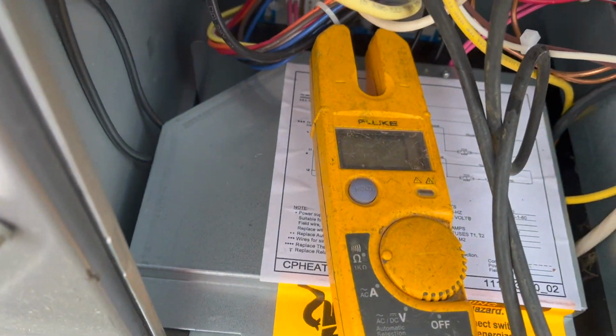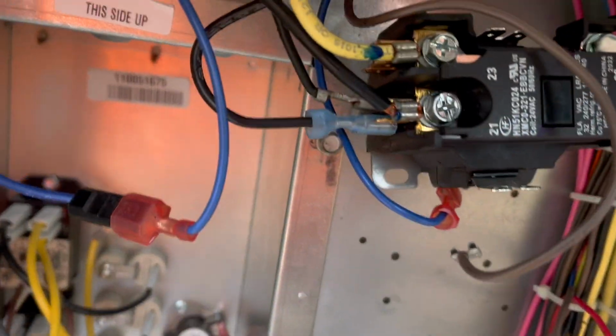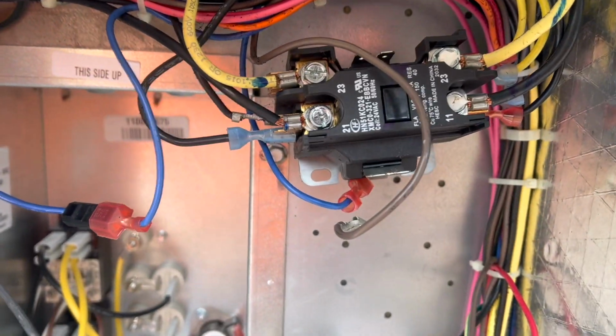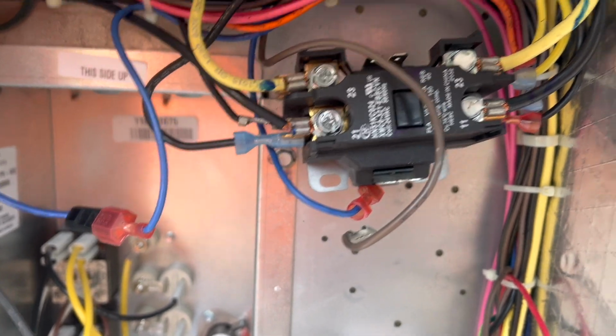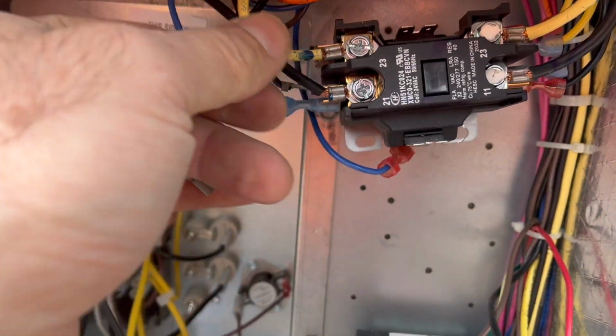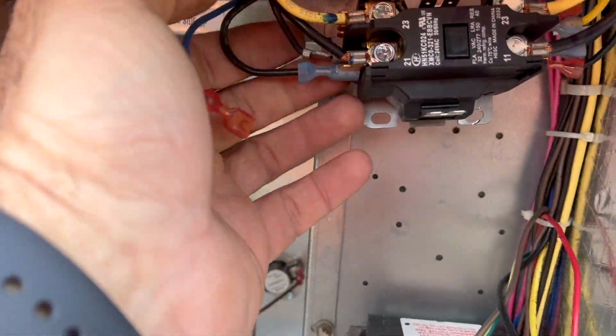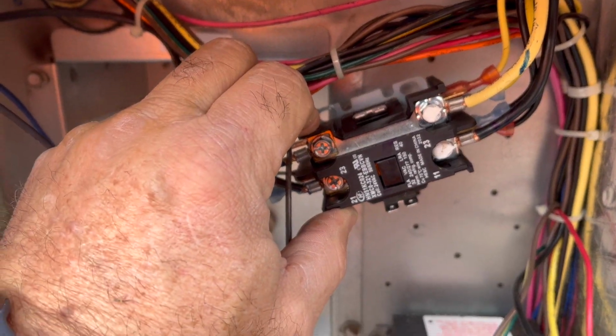I got it pulled down here where I can get on it good. We've got about 1 ohm, so that coil is pretty much a dead short. It's probably smoked. Well, it is smoked. I don't know if we'll be able to see it or not, but it's no good. If you put 24 volts on 1 ohm, you're gonna have way more amps than 3. So, save a fuse, check a contactor.